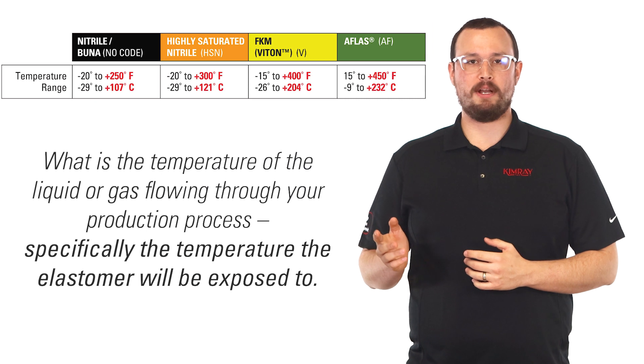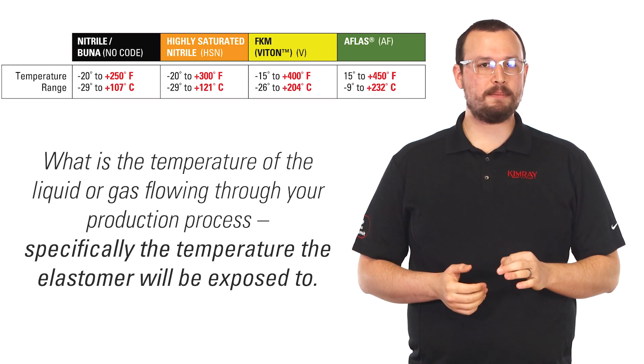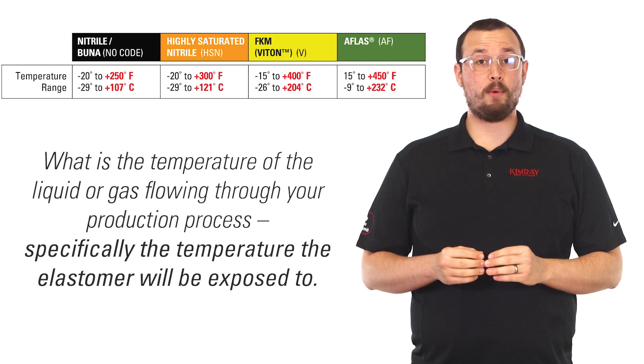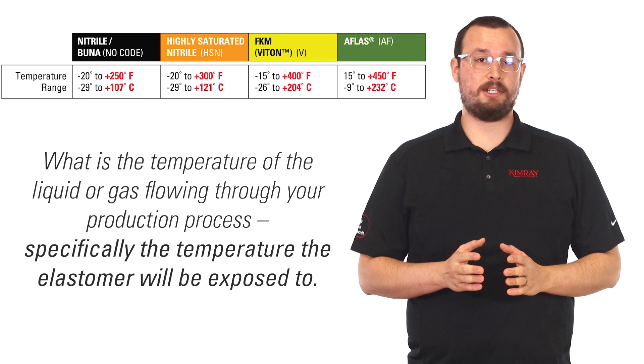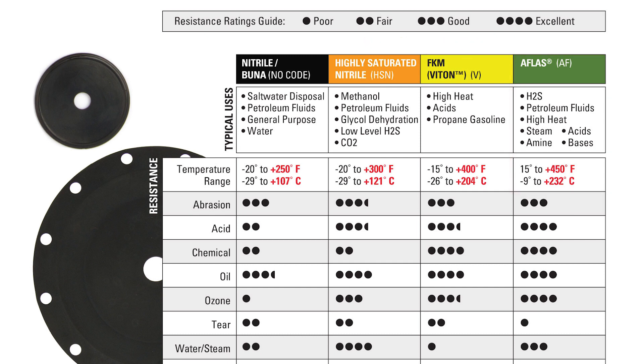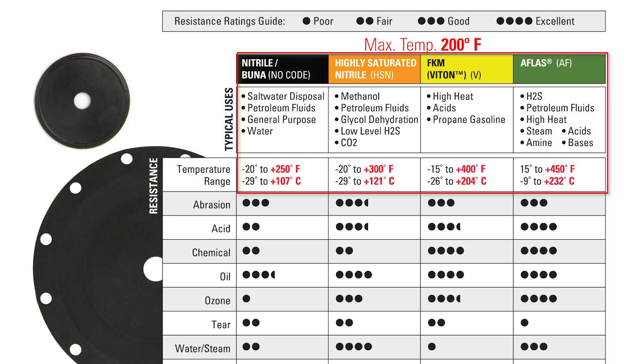To determine which elastomer to select for a given application there are three primary data points needed. First is operating temperature. What is the temperature of the liquid or gas flowing through your production process — specifically the temperature the elastomer will be exposed to? This is the first point you can use to narrow your selection. Production running at a maximum temperature of 425 degrees Fahrenheit may be limited to a single elastomer option, however based on temperature alone a 200 degree Fahrenheit operating temperature could still use any of these options.